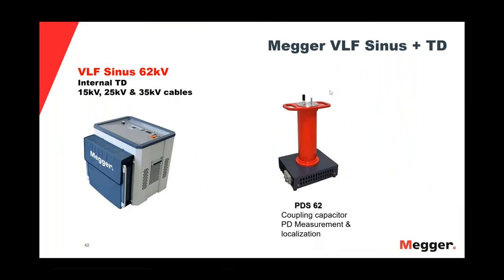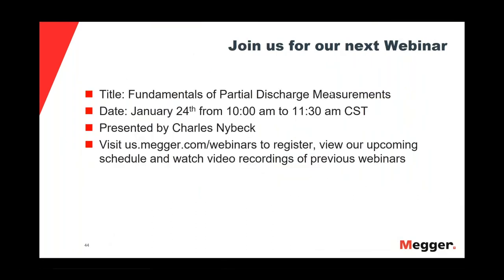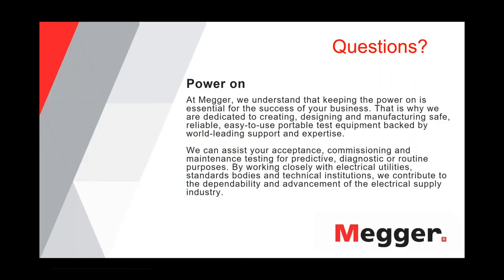Okay, so I hope I understood this correctly and everybody can hear me. For commissioning new cables, as Javier pointed out, the tan delta measures the aging condition of the cable. If you have a new cable, there is no aging, okay? And so the test is actually pretty ineffective on new cables. You will not measure anything, and what you measure, you expect that it is pretty low. And since the standard, as Javier also pointed out, has this traffic light philosophy, it's also not really necessary to have any sort of fingerprint or whatever. So for a commissioning test, tan delta is typically not necessary or not recommended.